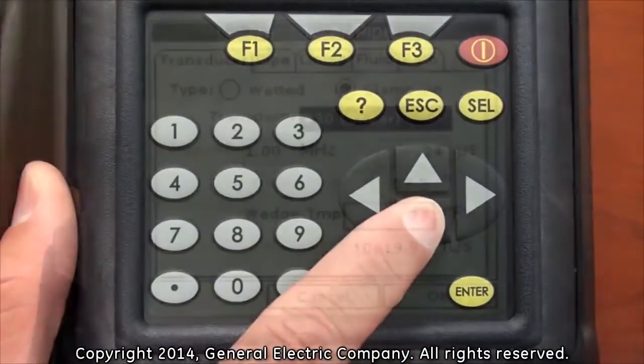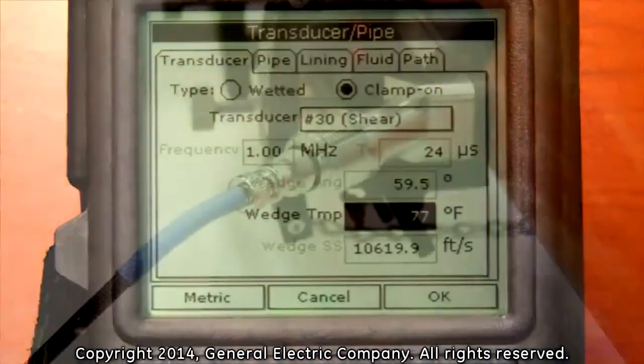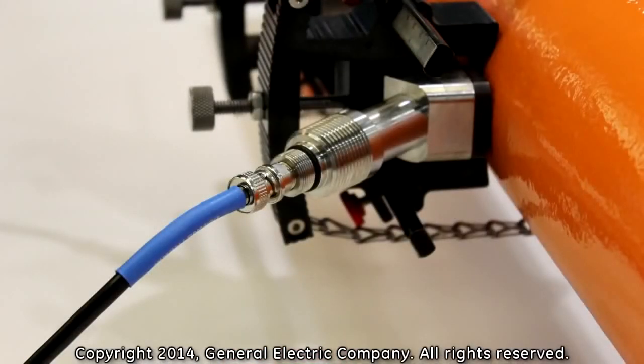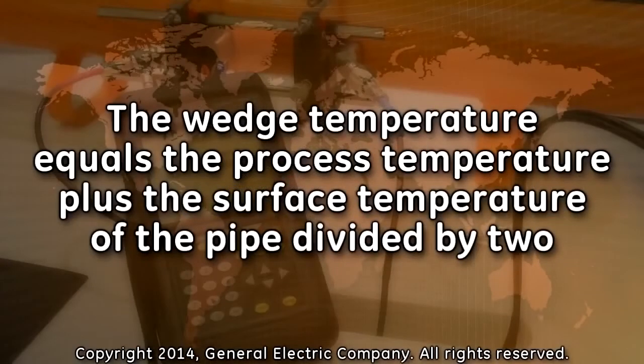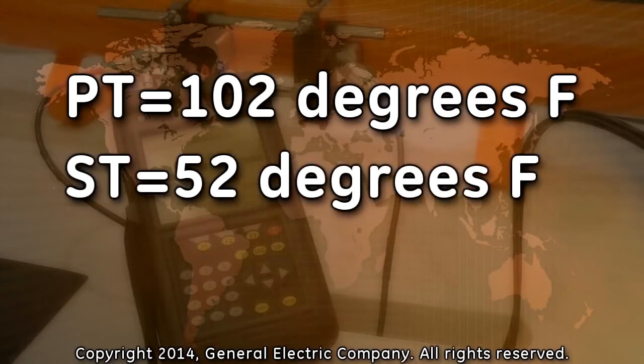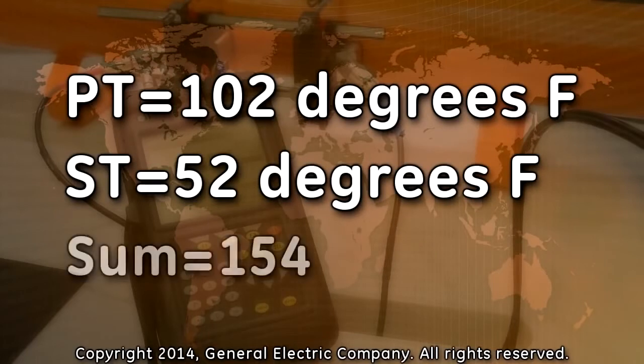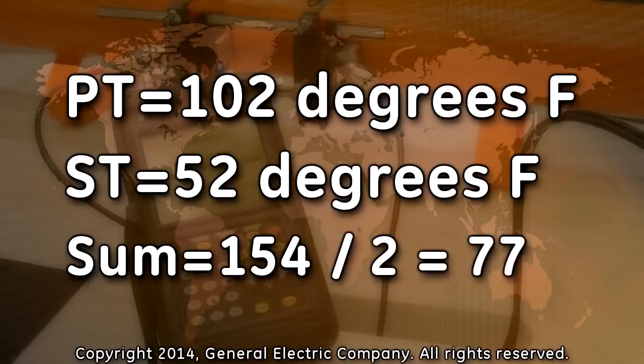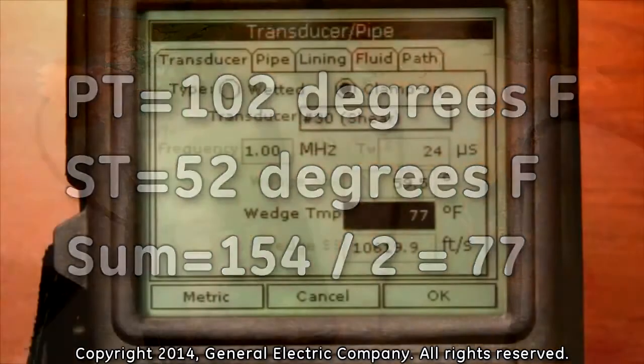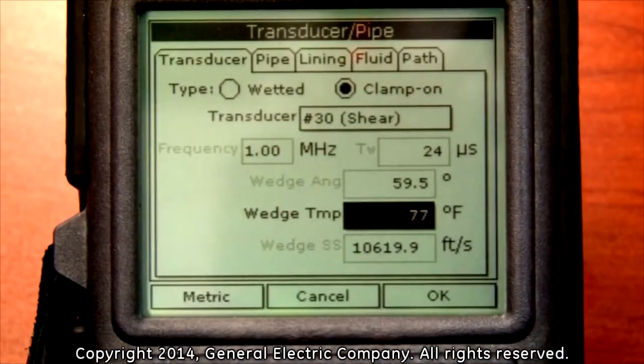Press the down arrow key on the keypad to highlight the wedge temperature input field. The wedge temperature is the temperature on the surface of the pipe that the transducer face is mounted to. The wedge temperature should be programmed for the process temperature plus the surface temperature of the pipe divided by 2. For example, if your process temperature is 102 degrees Fahrenheit and the surface temperature of your pipe is 52 degrees Fahrenheit, add 52 to 102 for a sum of 154. Then divide 154 by 2, which equals 77. This is the value that you input into the wedge temperature field, as in our example displayed on the screen.